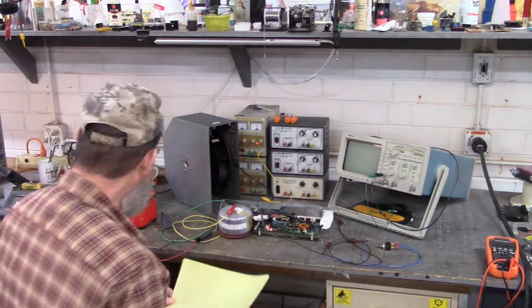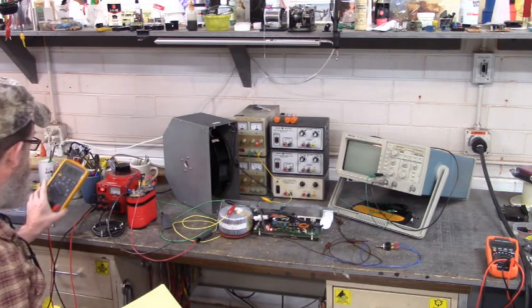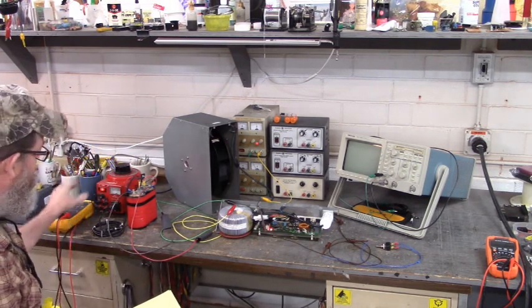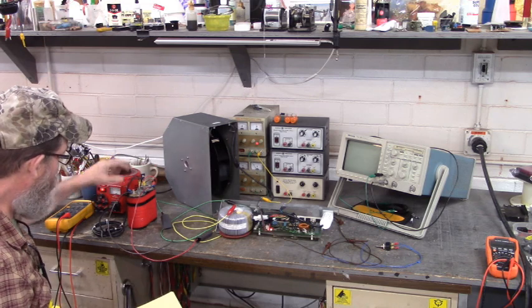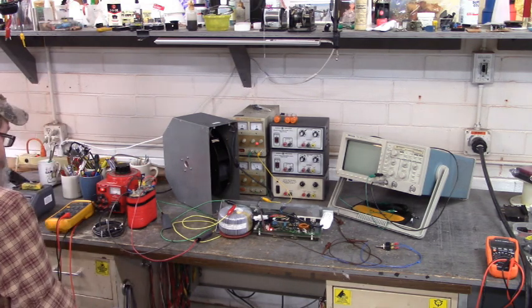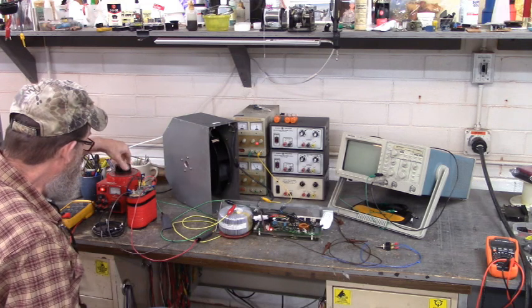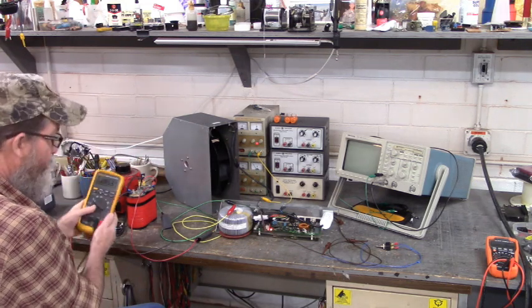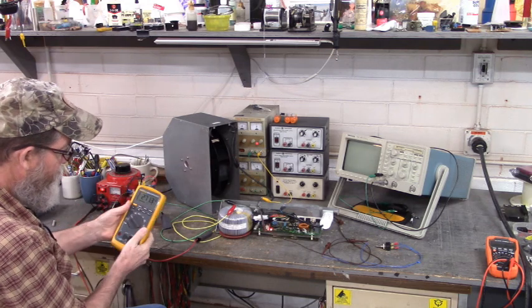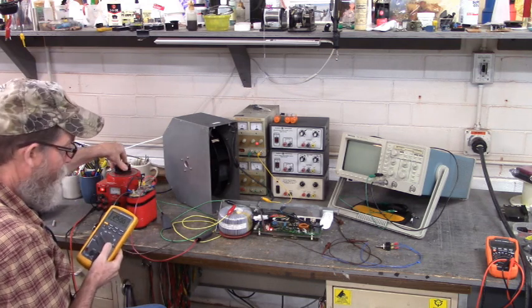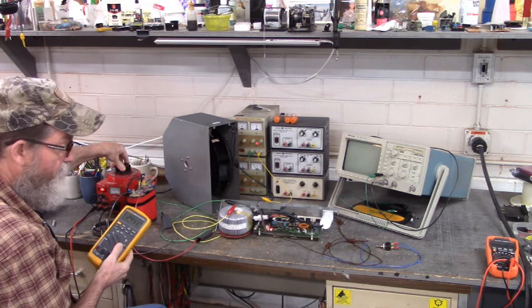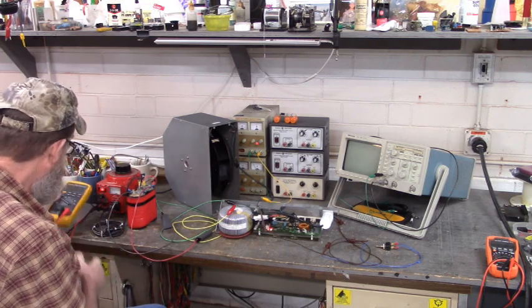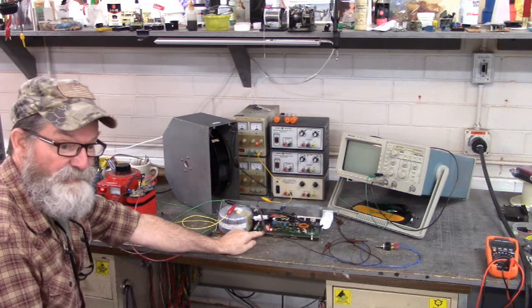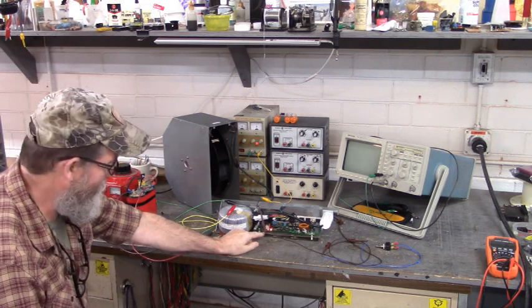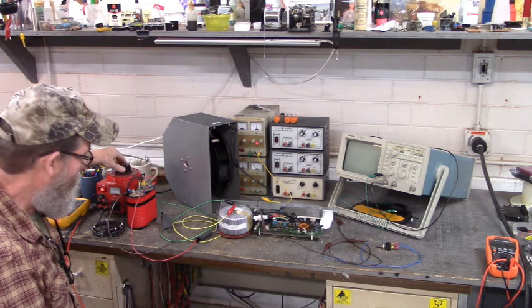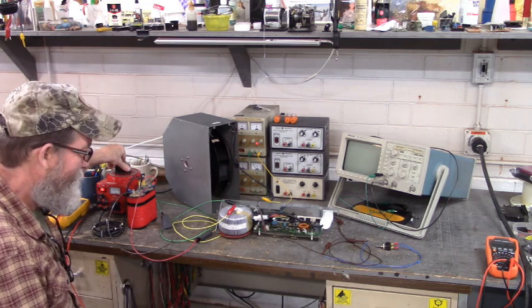Now what I did was, I have my meter connected on the plus and bus ground of the bus capacitors, the bridge rectifier, and while I was watching the meter and watching those LEDs, I snuck up on that 300 volts DC. And when those LEDs turned on, I stopped. I said, okay, I made it there. It's not an easy thing to do.